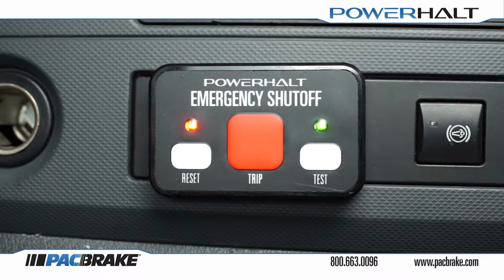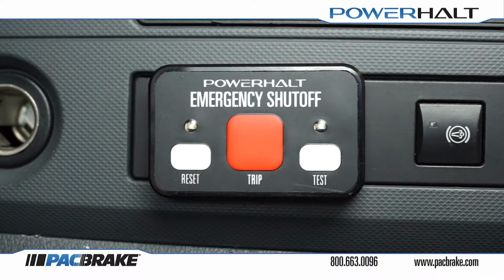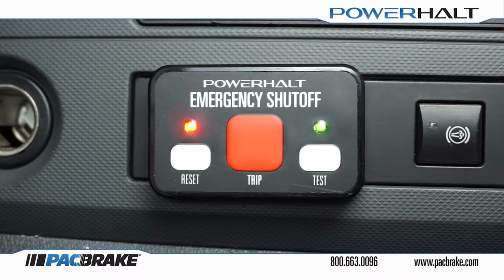Here we see the switch panel for a PH3 system that is in an error code state. The error code is displayed to the user by an initial rapid alternating flash of the red and green lights, followed by a number of simultaneous flashes of both lights. The number of simultaneous flashes corresponds to the error code. The sequence of flashes will continue until the issue is remedied and power is reset.